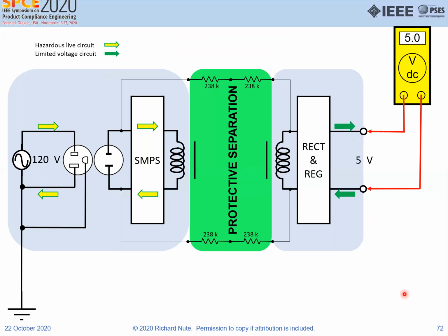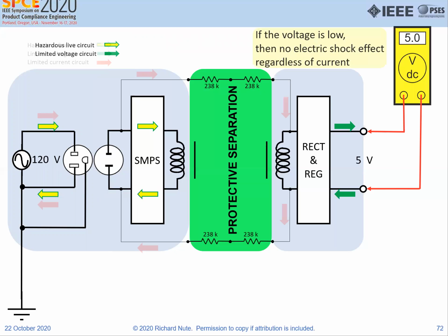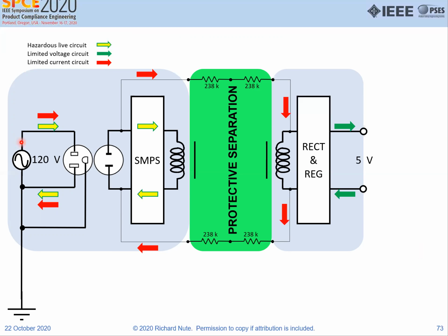And if we measure the voltage, we'll measure 5 volts DC. Okay. The voltage is low, no electric shock effect regardless of current. However, this thing has a limited current circuit shown by the red arrows. So the current comes through here, goes across the impedance, the protective separation. It's a pretty small current. Goes through the transformer, and depending upon how the circuit is physically laid out, returns this way, returns to the source.